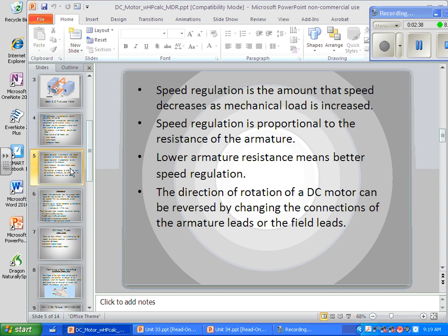Speed regulation is the amount of speed decrease as mechanical load increases. Regulation is proportional to the resistance of the armature. If we add resistance to just the armature — not the field winding — that will slow the rotation down. But if we put a resistor in the circuit going just to the field winding, it might actually try to run faster than its normal rotational speed.